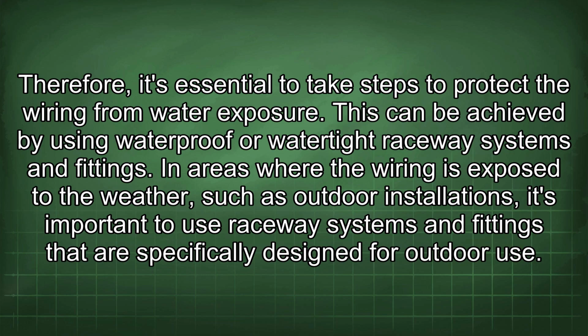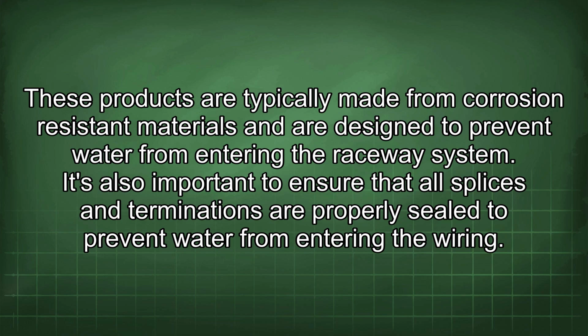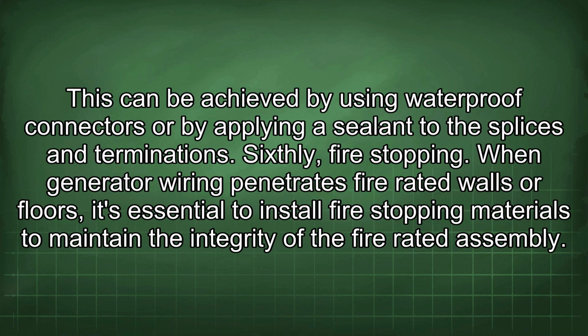In areas where the wiring is exposed to the weather, such as outdoor installations, it's important to use raceway systems and fittings that are specifically designed for outdoor use. These products are typically made from corrosion-resistant materials and are designed to prevent water from entering the raceway system. It's also important to ensure that all splices and terminations are properly sealed to prevent water from entering the wiring. This can be achieved by using waterproof connectors or by applying a sealant to the splices and terminations.